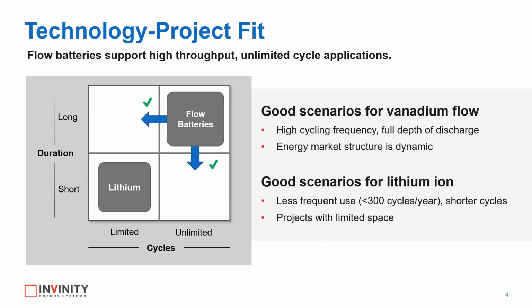Granted, a flow battery can handle less, it can handle 50 cycles per year, it'll be fine, but we find that our customers see the best economics when they get above 300 cycles per year, because there's no incremental degradation. These batteries don't degrade. They have a higher CapEx, but if you can really use them, like with the backhoe example, more than 300 cycles a year, we end up having a lower total cost of ownership over the project life.